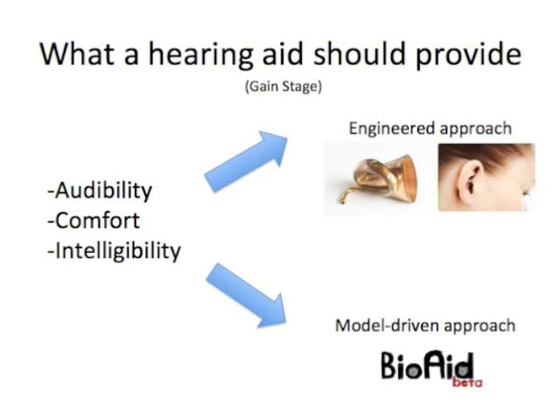You have to be careful when providing gain that you don't over-amplify sounds that are already audible, and you should maintain the cues that give you speech intelligibility. There are two ways of doing this: an engineered approach or a model-driven approach. Standard hearing aids on the market use the engineered approach, which has given us advancement from the ear trumpet through to the modern all-singing, all-dancing hearing aid. The general process is: measure a listener's sensitivity, apply gain in certain frequency regions, then use compression to prevent over-amplification. Fast compression doesn't sound particularly pleasant, so you mix in a slower compression to complement it, and you can refine further with look-ahead compression.